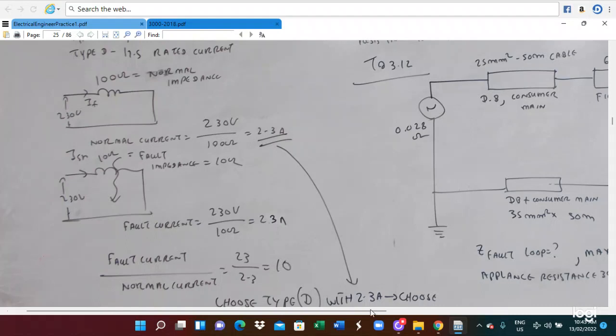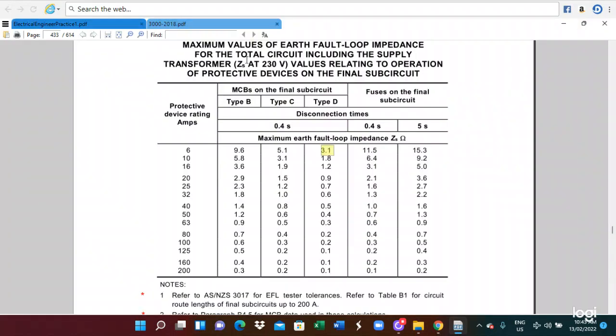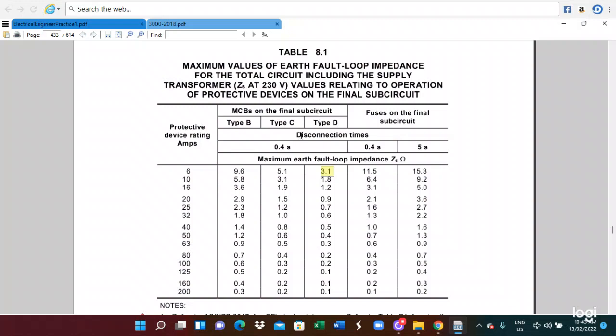Then you can look at the tables, table 8.1. So type D, 2.3. There is no 2.3. The minimum is 6, so you select 6 ampere and type D. So in this case, you find the fault loop impedance of 3.1. This is the way we find the fault loop impedance for this system.